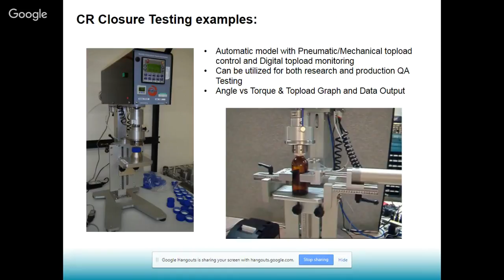The next slide was just another project where the customer was a cap manufacturer of child-resistant closures. They didn't care about the bottle, and they only wanted to verify or quality assure the caps. So they ended up coming up with a fixture that holds the cap, and they are testing the release torque and the reverse ratchet torque on this fixture. And this is fully automated. This does not have the manual actuation, but they dedicated this machine to this single cap only.